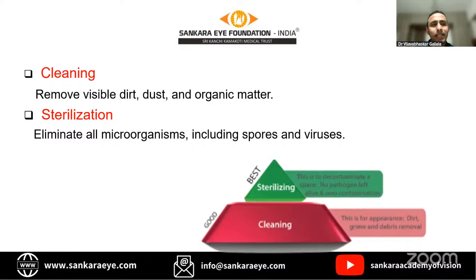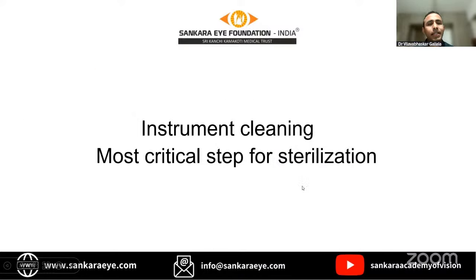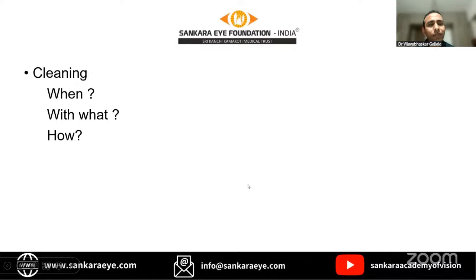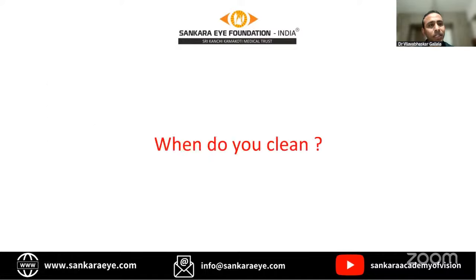Sterilization is not just sterilization, it's a part and parcel of cleaning, disinfection, and sterilization. Cleaning means removal of visible dirt, dust, and organic matter. And sterilization is a process which eliminates all microorganisms, bacteria, fungus, virus, and including spores. So instrument cleaning is the most critical step for sterilization. Let's discuss when we should clean, with what we should clean, what is the process, how we should clean.